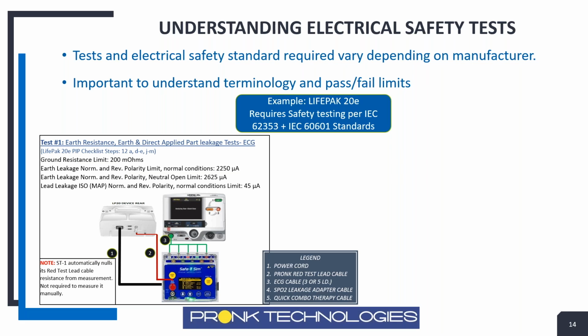The earth resistance, of course, we know, ground resistance. You're doing an earth and what's called a direct applied parts leakage test. Applied parts, of course, anything that gets applied to the patient. In this case, they want you to do it with ECG. And they lay out their pass-fail limits. And what's interesting here is they want a ground resistance of 200 milliohms. So that's okay. They want the ground resistance to be very low, to limit leakage as much as possible.